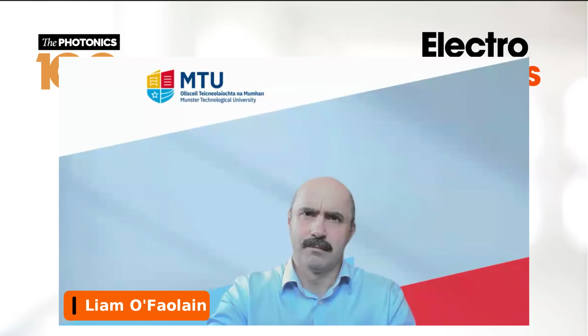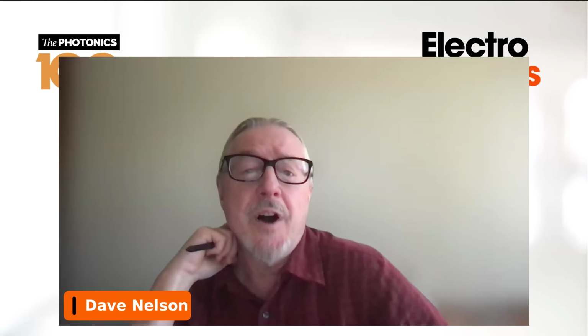So a general challenge of field measurements, you're not in a laboratory environment typically. And so a lot of optical instruments, maybe not all, but a lot of them have thermal dependencies on their calibration. And so temperature stabilization can be a serious challenge for many instruments, or if you can't stabilize it, being able to understand the calibration as a function of temperature is really important. For larger instruments, this can also couple with power requirements in the field.